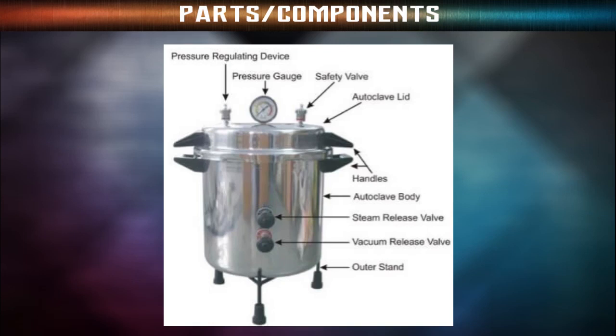A pressure gauge is present on the lid of the autoclave to indicate the pressure created in the autoclave during sterilization. The pressure gauge is essential as it ensures the safety of the autoclave and the working condition of the operation. Pressure releasing unit or whistle. A whistle present on the lid of the autoclave is the same as that of the pressure cooker. The whistle controls the pressure inside the chamber by releasing a certain amount of vapor by lifting itself.